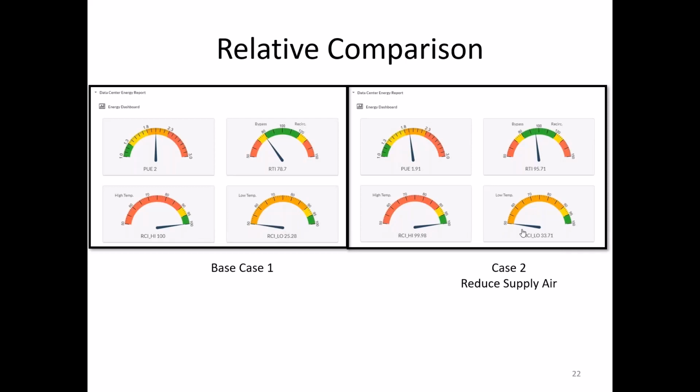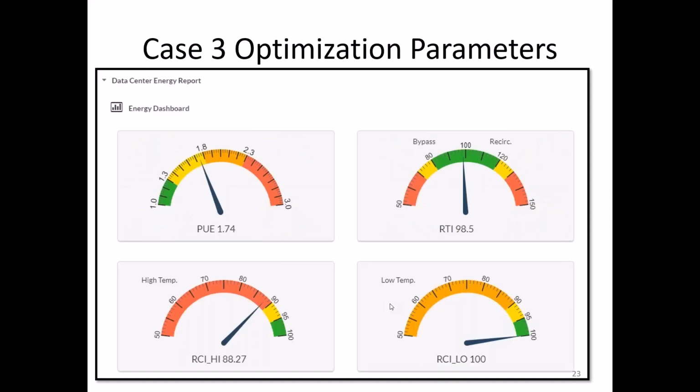So that tells us that we're getting a little bit better. We've still got temperature problems. We're getting close to being optimized on the racks themselves compared to the air handlers, but we've still got some issues. So we'll take the next step here on this one.